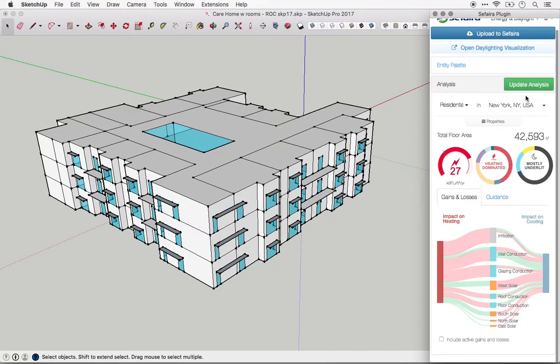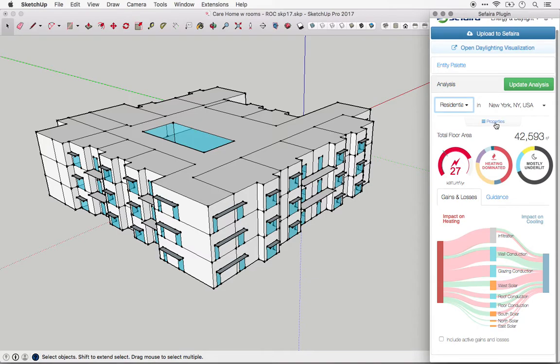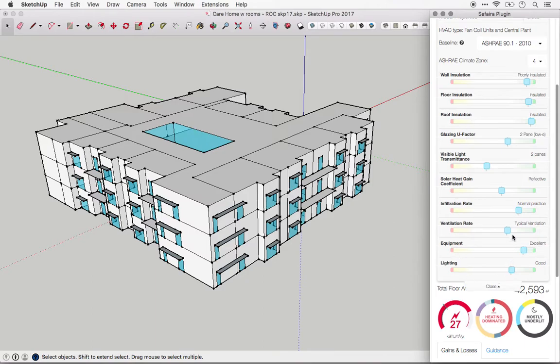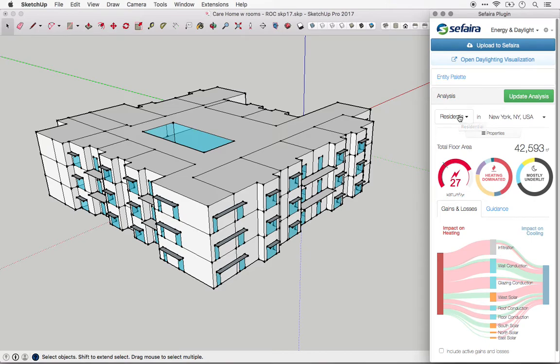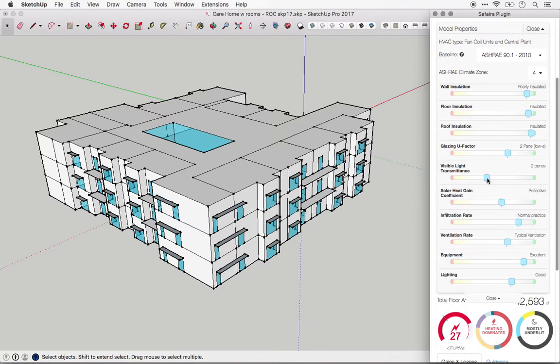Now let's dive into each of those three inputs a little bit further. The use type governs things that are associated with the building use—elements like lighting power density, equipment power density, and ventilation rate. Now those three properties you can actually adjust in the properties panel of the plugin. You'll see them at the bottom here. The use type also affects other inputs that are not able to be edited in the plugin, such as the occupant density of the space or the operating schedule. Those elements you can modify in the web application. If the use type that you're looking for doesn't show up in this list, a good workaround is to select the one that most closely matches the schedule of your building, and then go into the properties panel and adjust the ventilation rate, equipment power, and lighting power to more accurately reflect the building that you're trying to model.